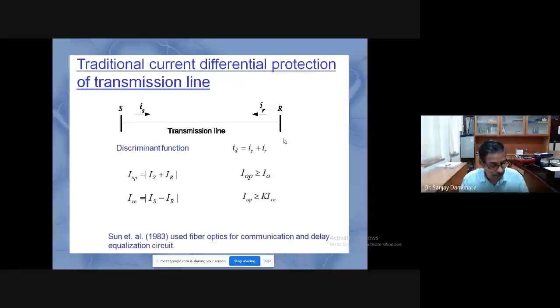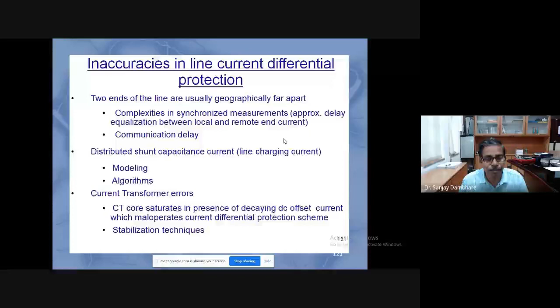And of course, during no fault condition, because of the line charging current, the difference between the sending end and the receiving end is not zero. This can be handled, right? This can be handled. So this is what I was saying, the complexities in synchronous measurement. But fiber optic technology for data communications and the global positioning system for time synchronization have asked the protection engineer to think of differential protection as an option even for transmission system protection, and that is how you could see that there are many researchers working in this area.